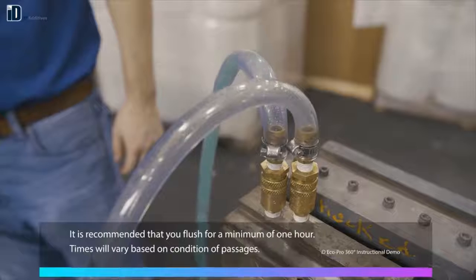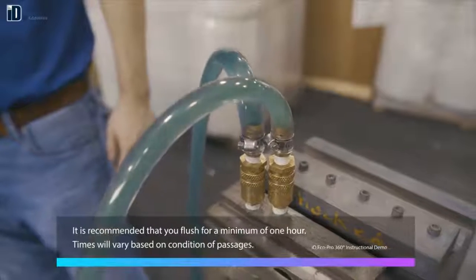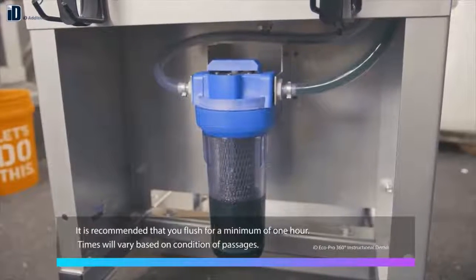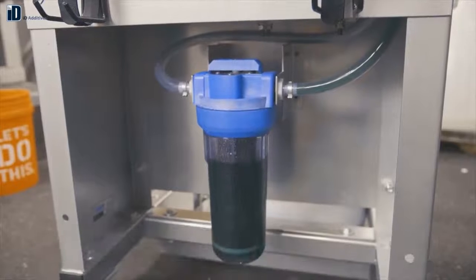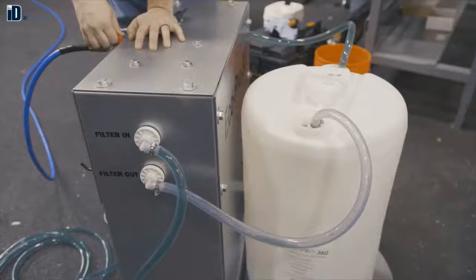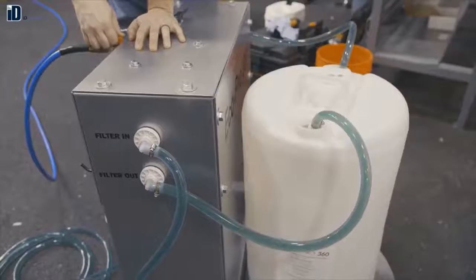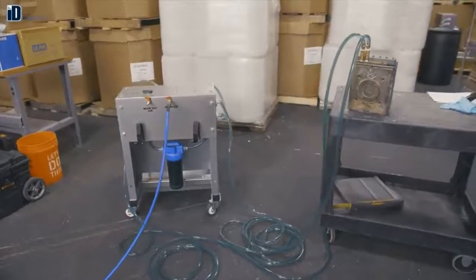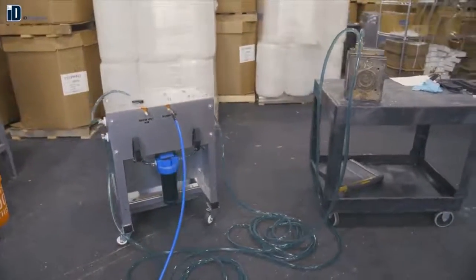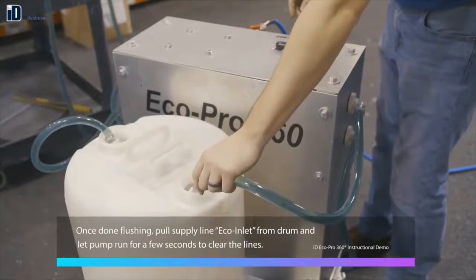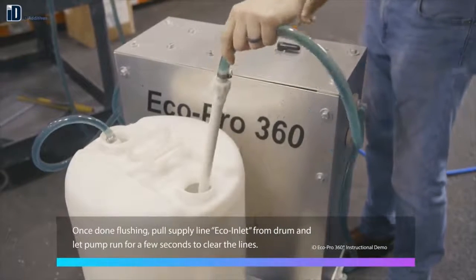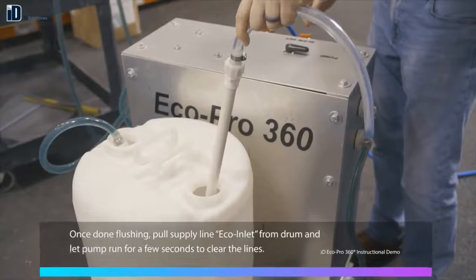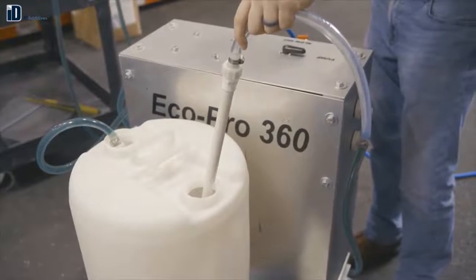It is recommended that you flush for a minimum of 1 hour, although times will vary based on the condition of your cooling passages. Once you're done flushing, pull the supply line labeled Eco Inlet from the drum containing the material and let the pump run for a few seconds to clear the lines.